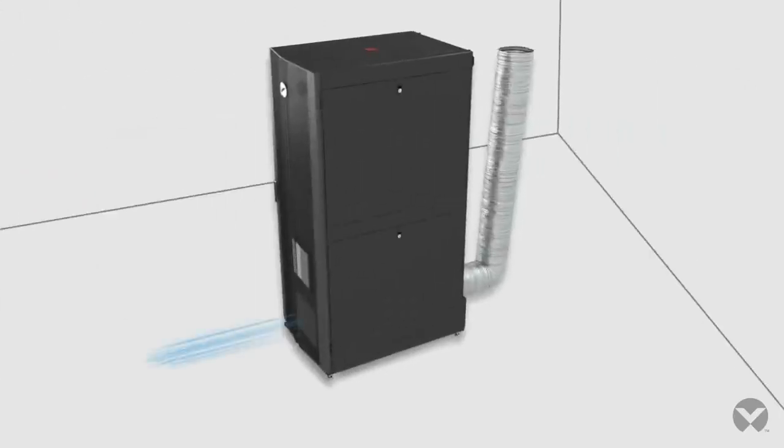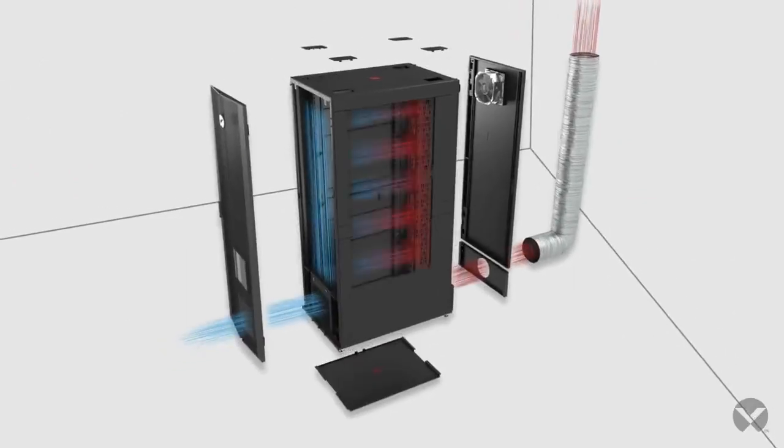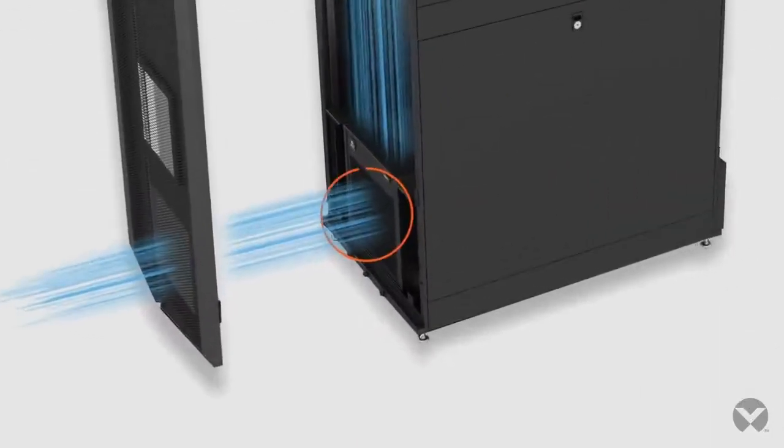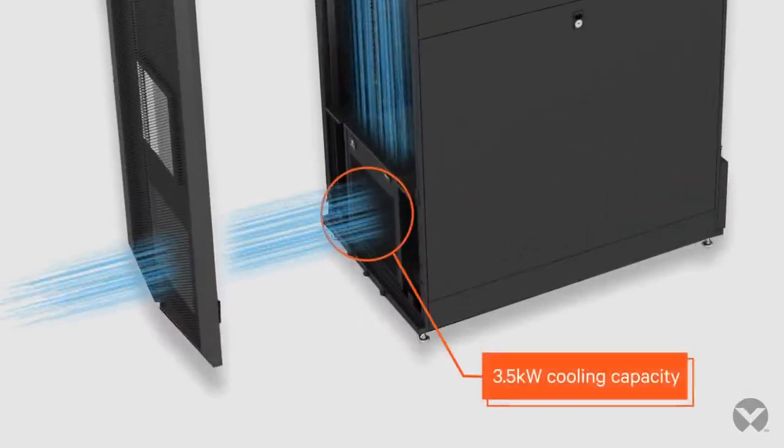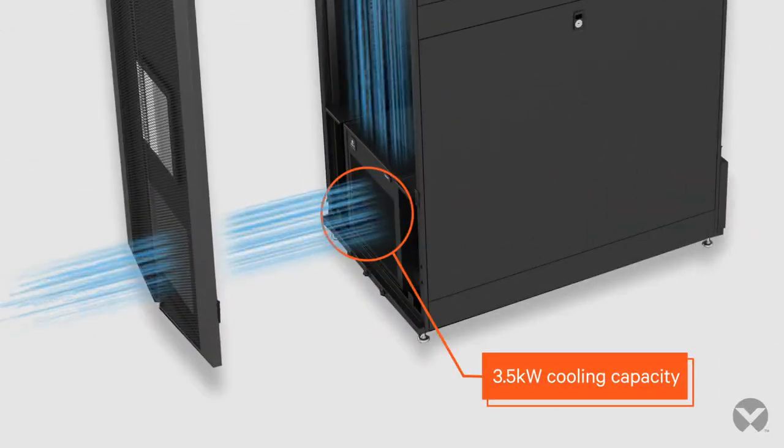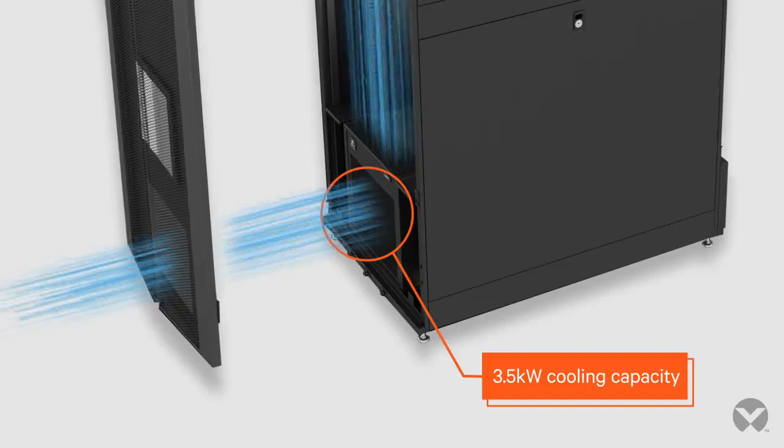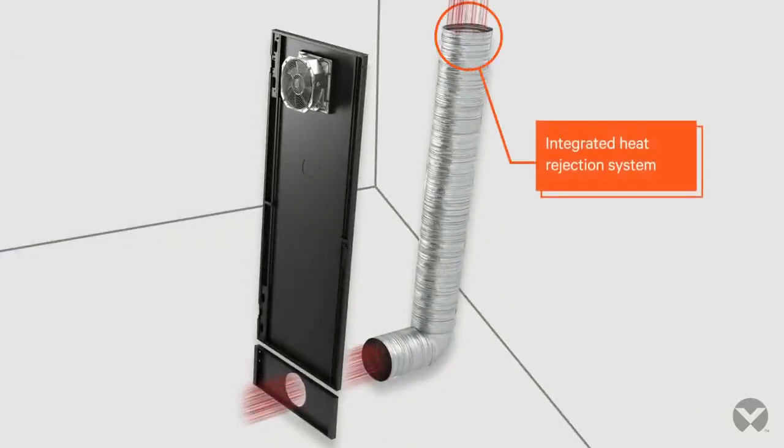VRCS enclosure provides a unique pseudo-hot-cold aisle inside the rack for efficient airflow and prevention of hotspots where your equipment breathes. The self-contained rack cooling kit comes pre-charged with refrigerant in a space-saving plug-and-play kit that mounts easily in the bottom of the enclosed rack. Integrated heat rejection system that contains hot air in the rear of the self-contained rack and rejects it into a drop ceiling.